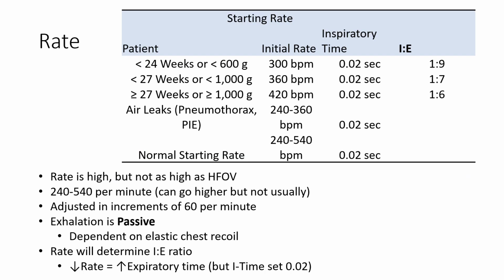While the jet ventilator utilizes high respiratory rates, the rates are generally lower than high-frequency oscillatory ventilation. When rate changes are made on the jet ventilator, they should occur in increments of 60 for each move. The inspiratory time is typically set at 20 milliseconds and is not routinely changed as it can easily lead to air trapping. By setting a consistent I time, the rate will determine the I to E ratio and exhalation time. Exhalation on the jet ventilator is passive, meaning it is dependent on elastic recoil. This requires the rate to be lower than the high-frequency oscillatory ventilator to allow for an adequate exhalation time.